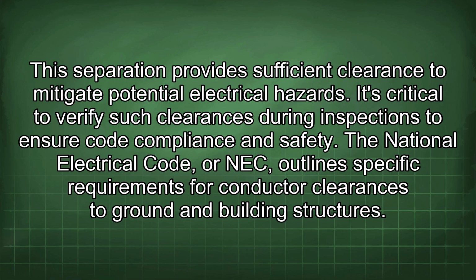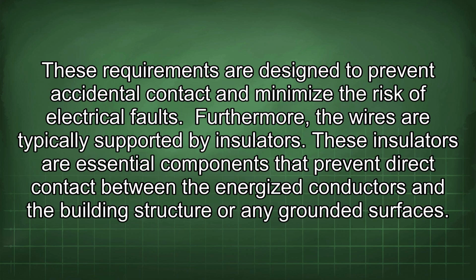It's critical to verify such clearances during inspections to ensure code compliance and safety. The National Electrical Code, or NEC, outlines specific requirements for conductor clearances to ground and building structures. These requirements are designed to prevent accidental contact and minimize the risk of electrical faults.